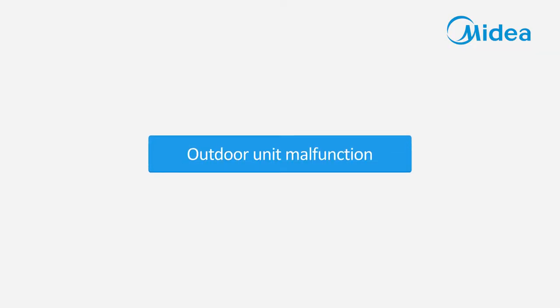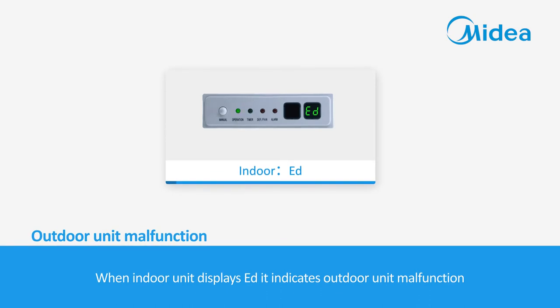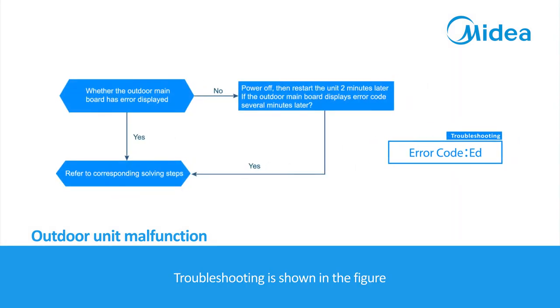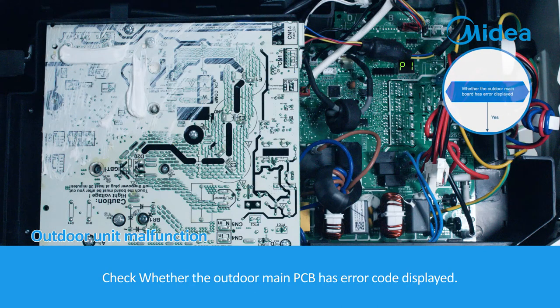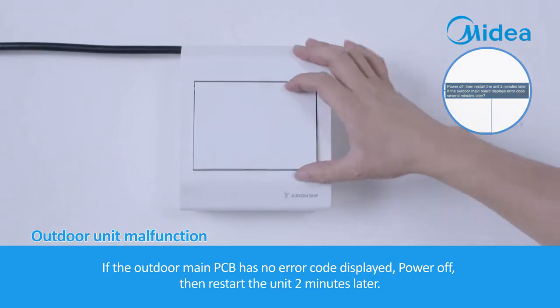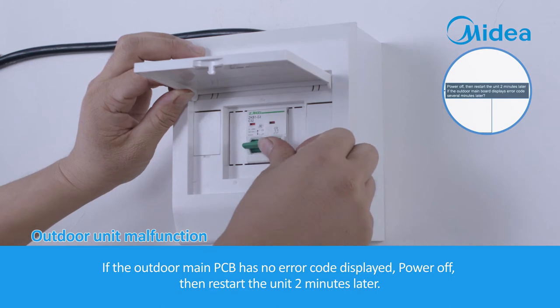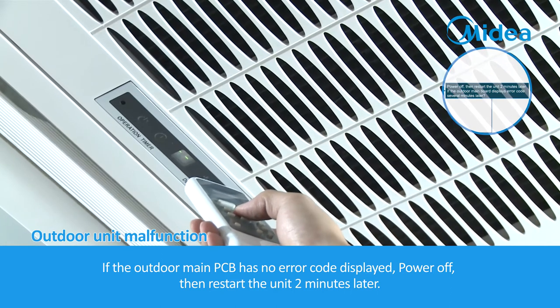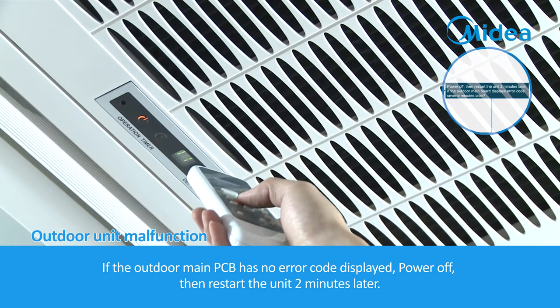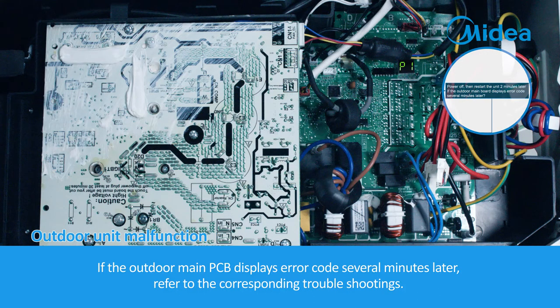Outdoor unit malfunction. When the indoor unit displays ED, it indicates an outdoor unit malfunction. Troubleshooting: check whether the outdoor main PCB has an error code displayed. If no error code is displayed, power off, then restart the unit 2 minutes later. If the outdoor main PCB displays an error code several minutes later, refer to the corresponding troubleshooting procedures.